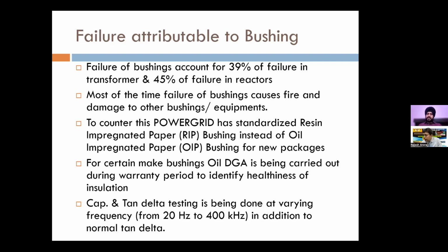Another method to capture this incipient fault is variable frequency tan delta. So here we have seen that if there is any moisture ingress in the bushing, OIP bushing particularly, then at lower frequency level, the tan delta values are comparatively higher. So this is how we have managed to bring down our failure rate.